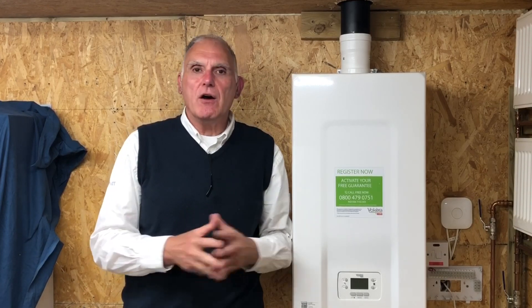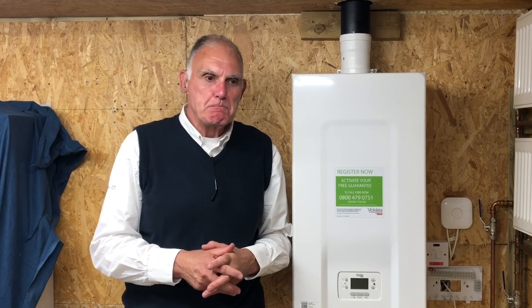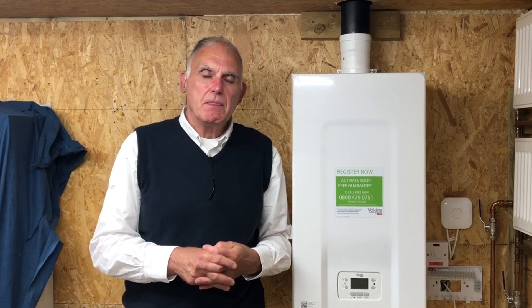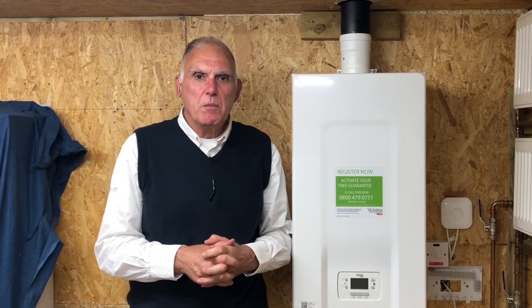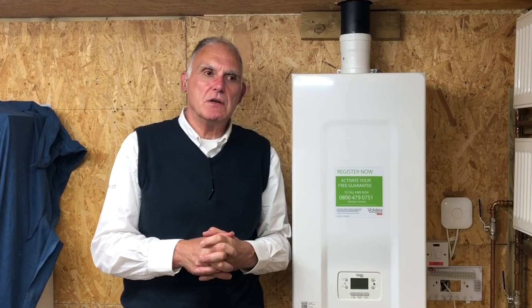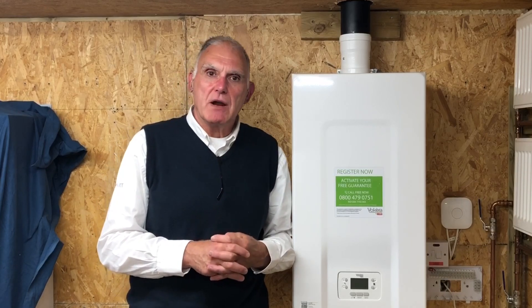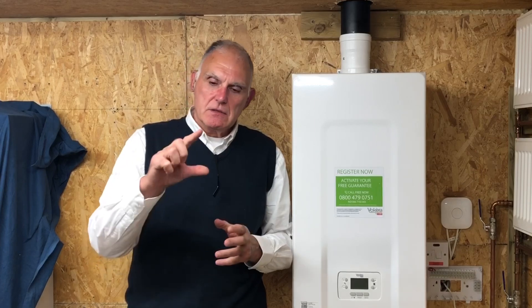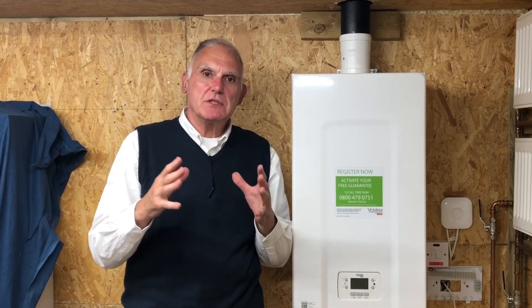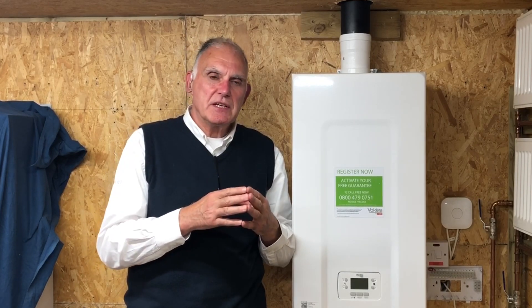Alan's asked me to do a short resume of control options on our boiler. Most boilers can be switched by a standard on/off thermostat, but there are options for OpenTherm control and weather compensation. The benefit of operating with OpenTherm or weather compensation is it runs the boiler slightly more efficiently, as it monitors and regulates the boiler flow temperature and return temperature. Condensing boilers operate more efficiently the cooler they run. With an ordinary thermostat, the contacts close, the boiler works up to its maximum temperature, stops, waits, and comes back on again — and that maximum temperature would be so hot that the boiler wouldn't condense.